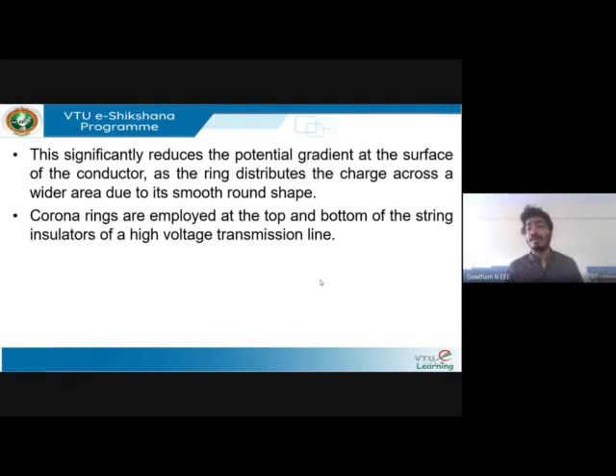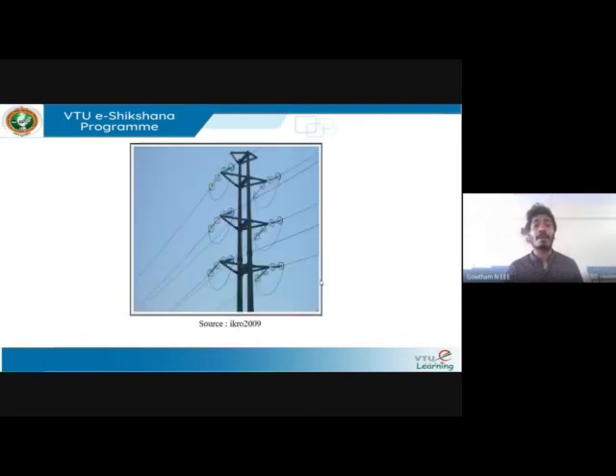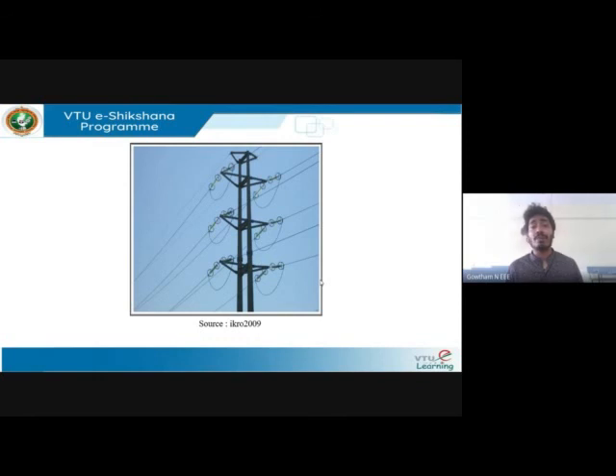Corona rings are employed at the top and bottom of the string insulators of high voltage transmission lines. String insulators are made of porcelain — when discharge occurs, the porcelain material gets damaged and its life cycle is reduced. This diagram shows where corona rings are employed at the sharp ends, reducing the potential gradient and stress, thereby reducing the effect of corona on the line.